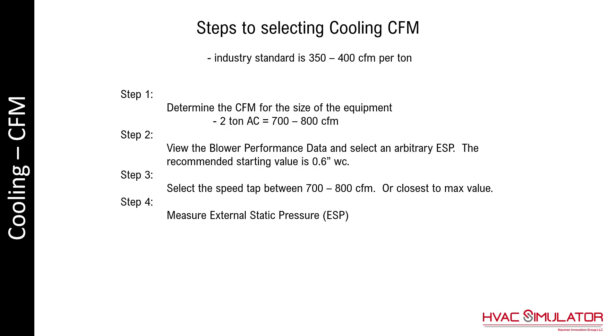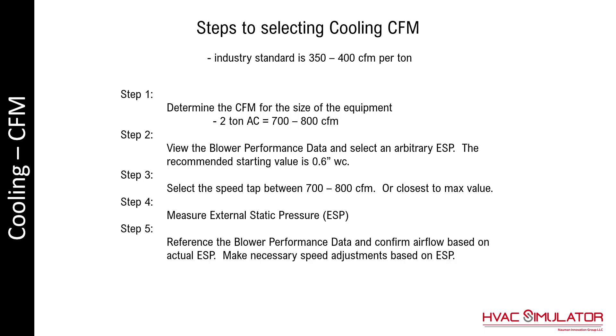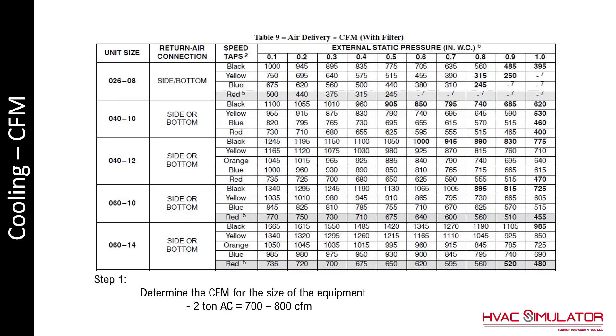Measure the external static pressure. Then reference the blower performance data and confirm airflow based on the actual external static pressure. Make necessary speed adjustments based on the external static pressure.